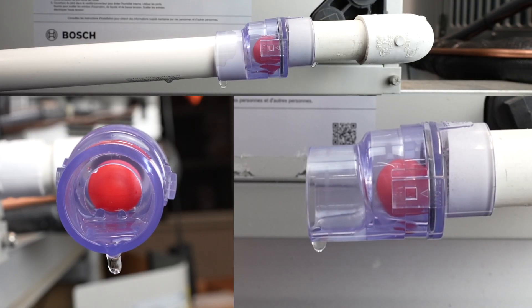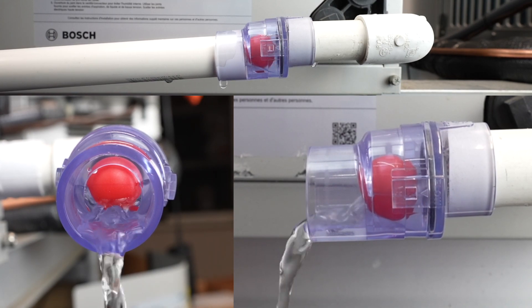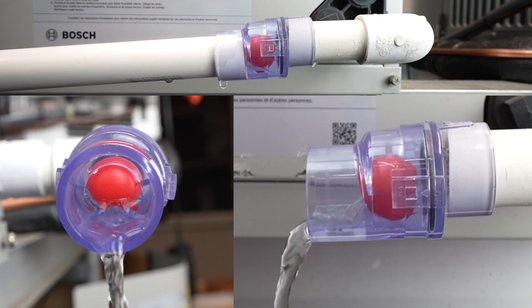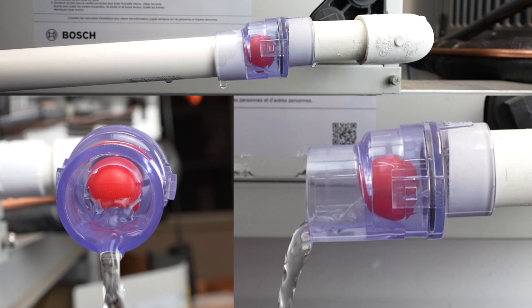The W-Trap was designed for negative pressure systems. When the fan turns on, it pulls the ball valve tight against the 3/8 hole, sealing the condensate line. Once condensate builds up, it will push the ball valve away from the hole, up the standoffs, allowing the condensate to flow freely past.